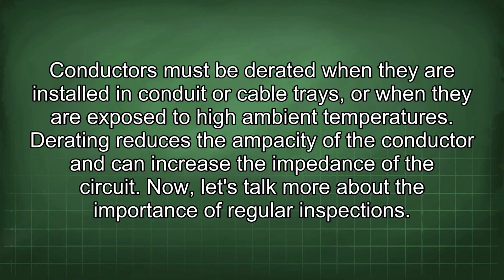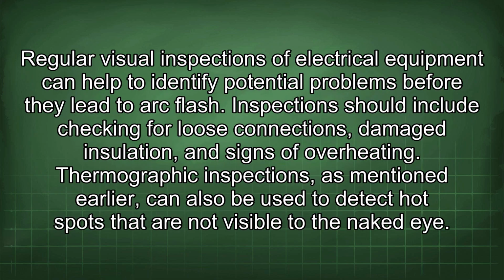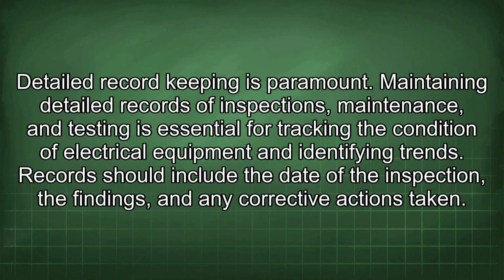Now, let's talk more about the importance of regular inspections. Regular visual inspections of electrical equipment can help to identify potential problems before they lead to arc flash. Inspections should include checking for loose connections, damaged insulation, and signs of overheating. Thermographic inspections, as mentioned earlier, can also be used to detect hot spots that are not visible to the naked eye. Detailed record keeping is paramount. Maintaining detailed records of inspections, maintenance, and testing is essential for tracking the condition of electrical equipment and identifying trends. Records should include the date of the inspection, the findings, and any corrective actions taken.